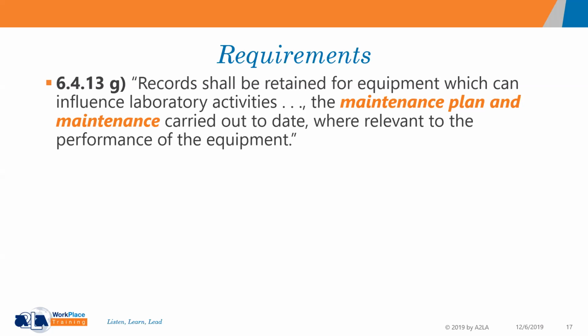So I asked the technician to determine if the instrument temperature was an issue, and whether the temperature was out of tolerance. Sure enough, when he looked at the information that was logged on the electronic device, it was out of tolerance. So he was making bad measurements. Had I not brought that up, it could have caused failures for our customers. Either it was failing and is now passing, or it was passing and should be failing. So the moral of the story is that we need to understand how maintenance impacts the measurement accuracy and the measurement uncertainty of the measurements that we are making.